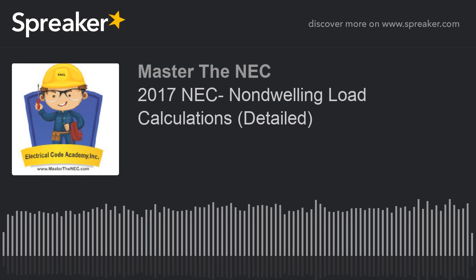So I might have a unit 1 load for the assembly hall and auditorium, but when it comes to the hallways, the corridors, and various closets, and even the stairway, that's different. That is a half of a VA, volt ampere per square foot. So in this case, it would be a 0.5 per square foot, all right? A 0.5 VA. So you see that I can pick and choose and dissect different portions.